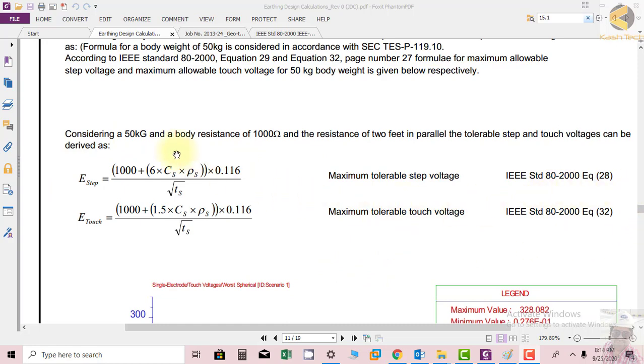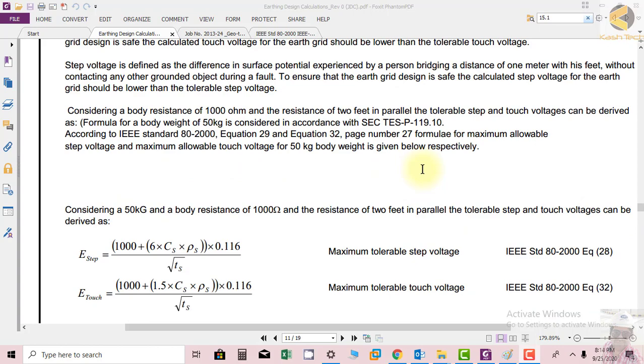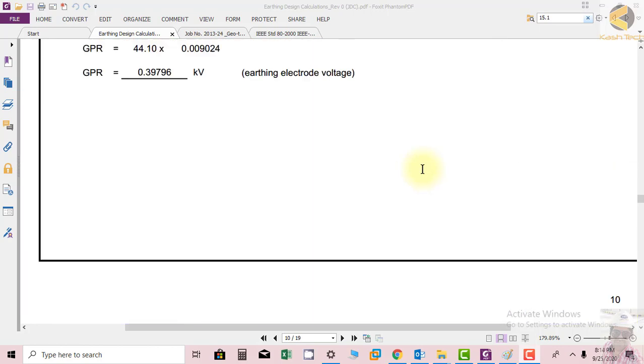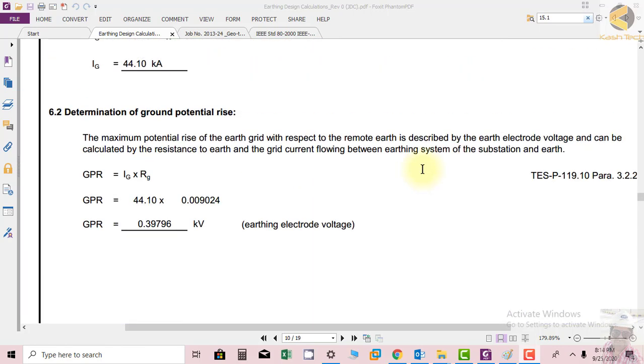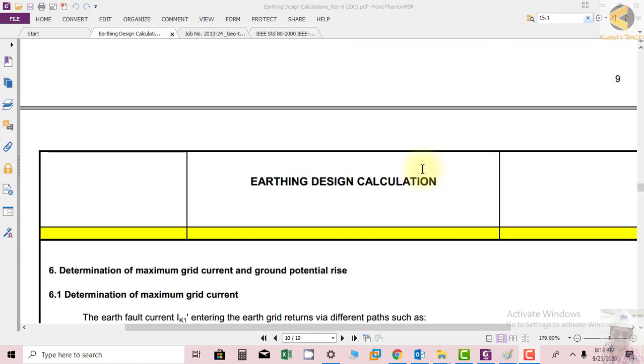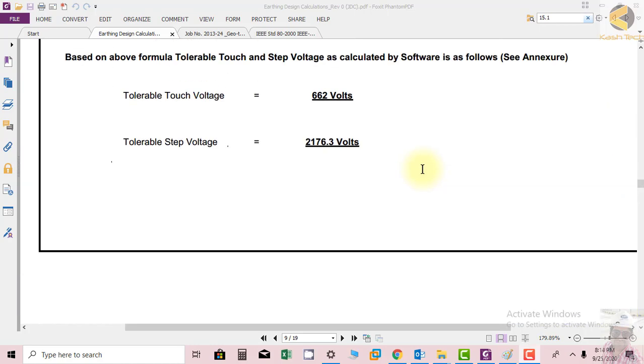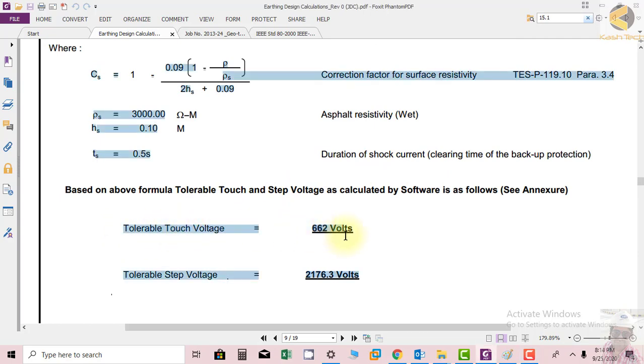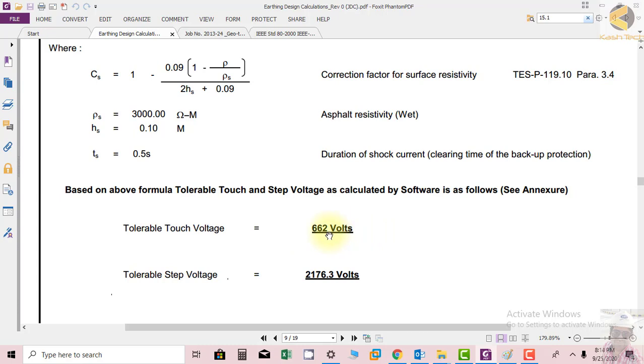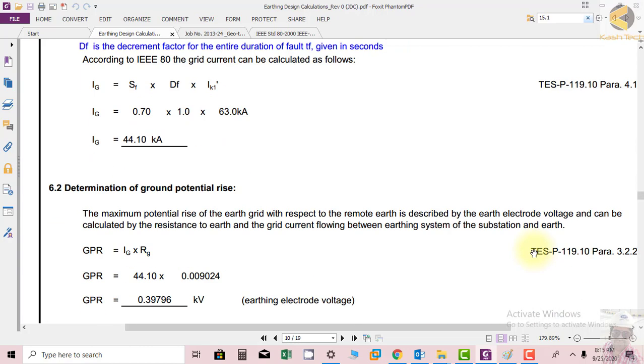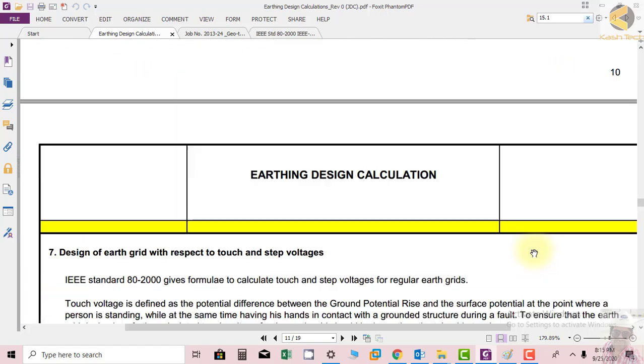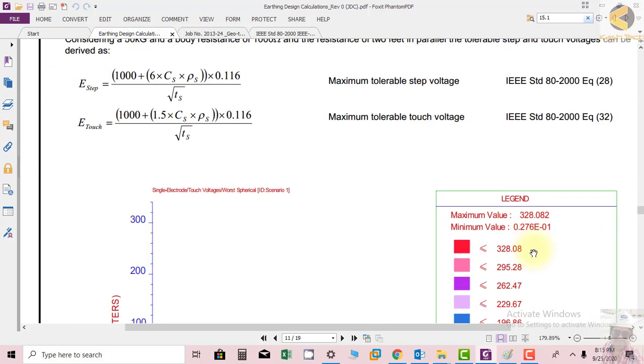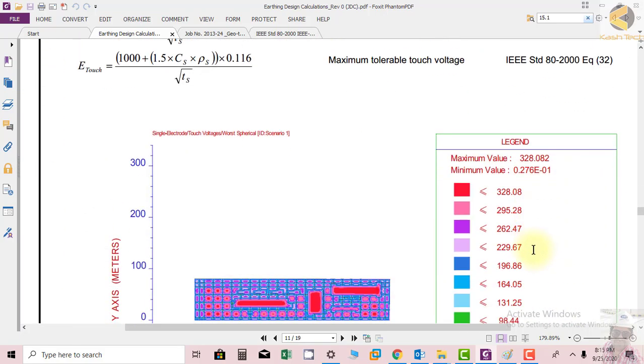If you remember from the previous section, we calculated these values. Allowable touch potential is coming as 662 volts maximum, and tolerable step voltage is coming as 2176 volts. Now we have put the parameters in the software and we get the result for touch voltage magnitude.